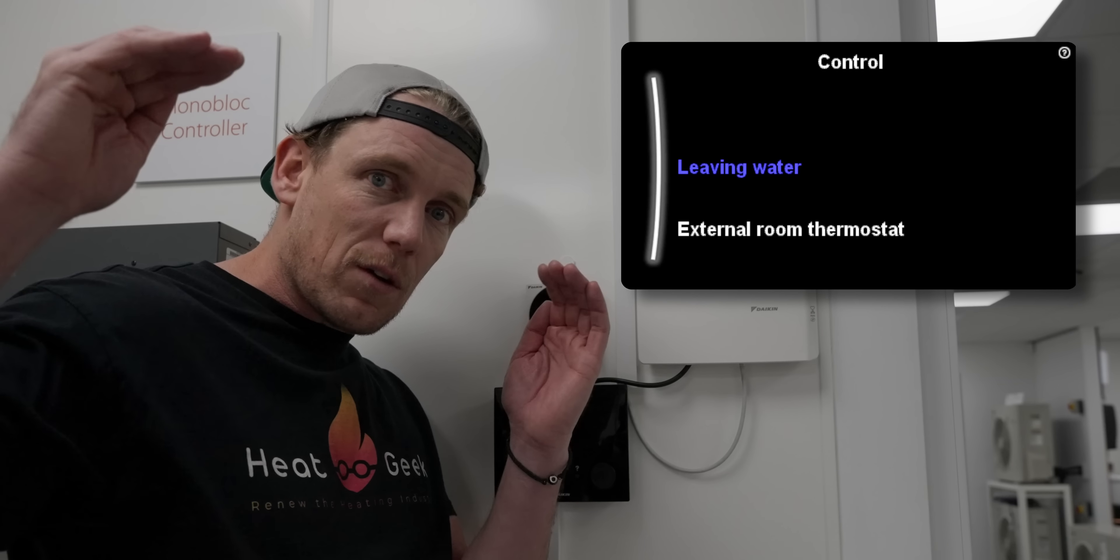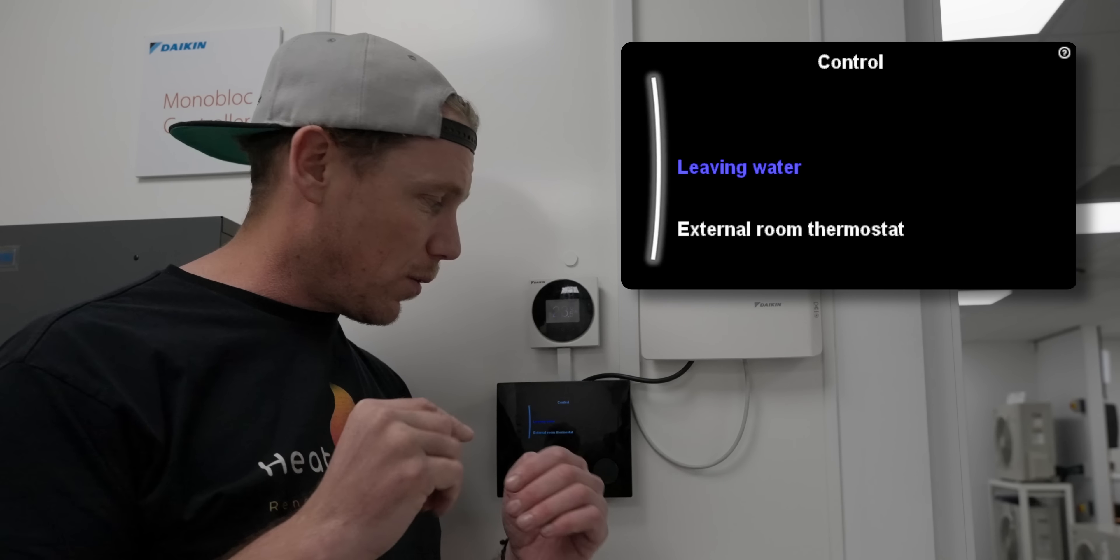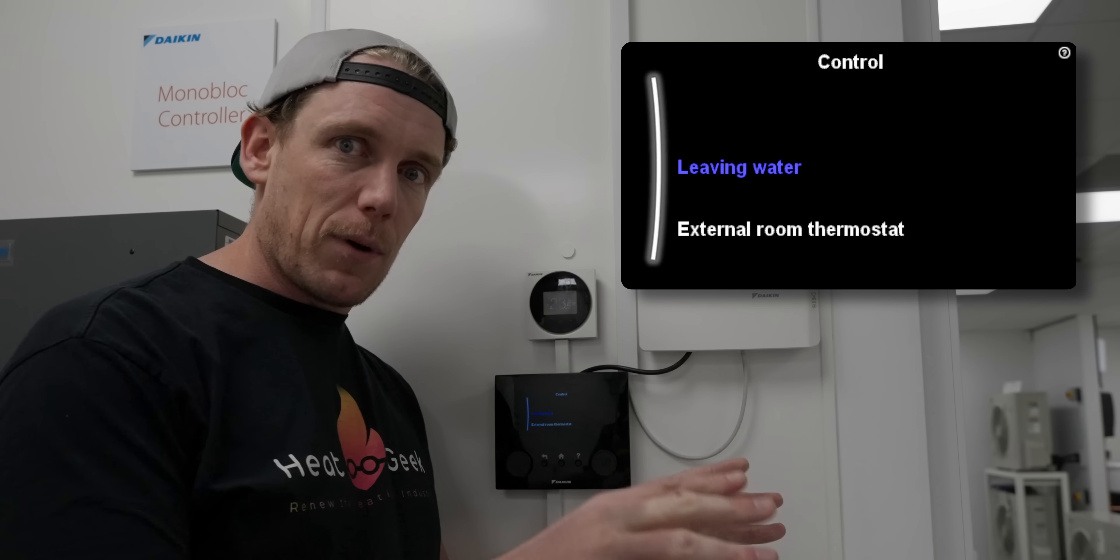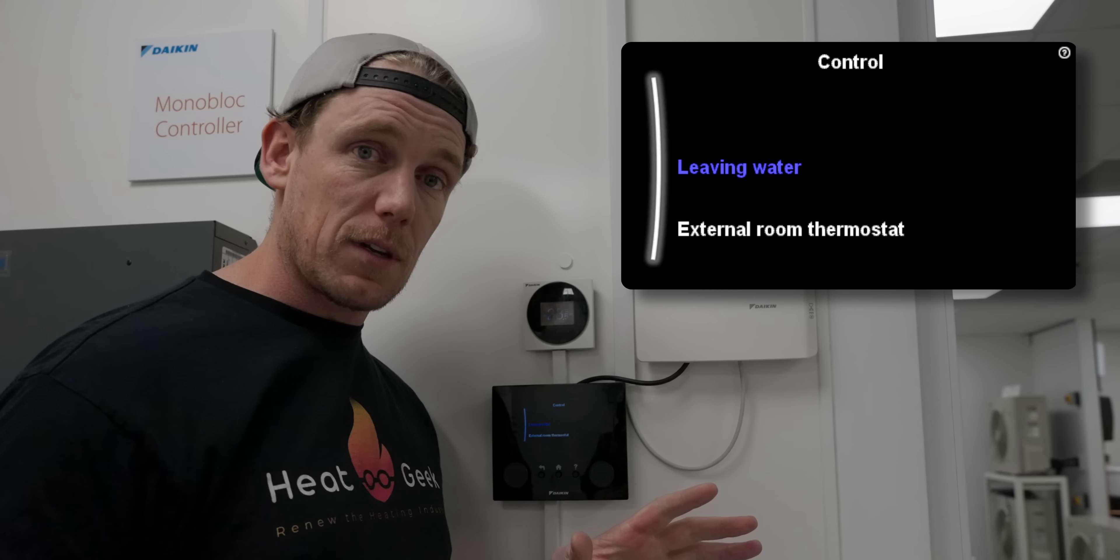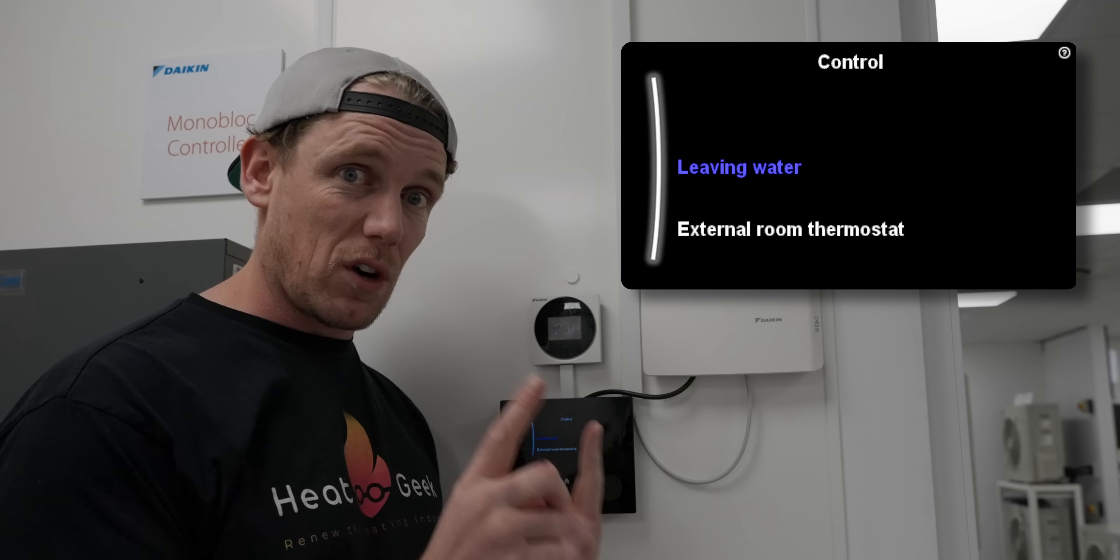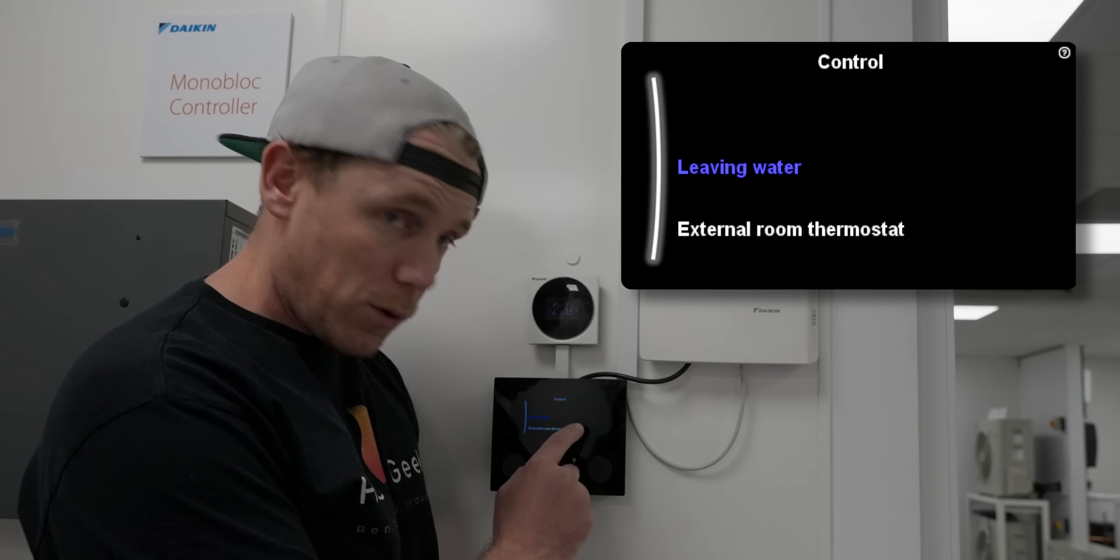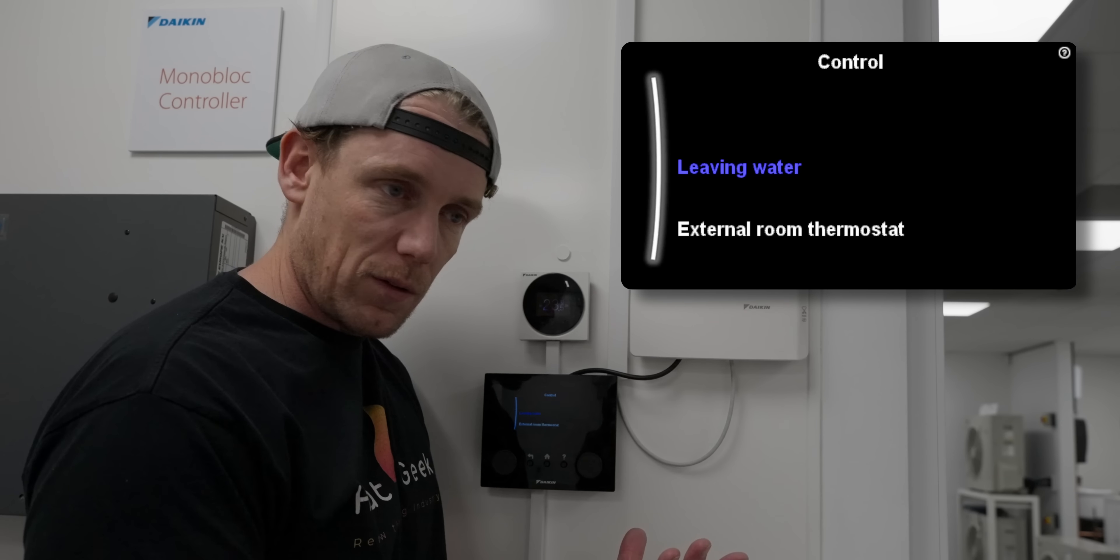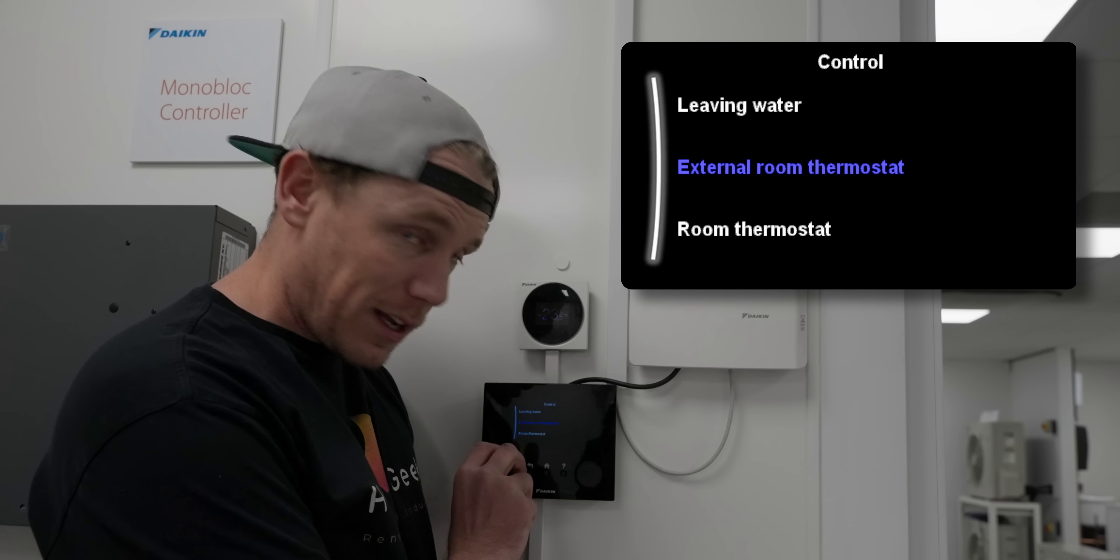Get it as comfortable as possible, then you can bring in your external controls so they close down the actuators as little as often and let the heat pump pump around as much of the system continually as possible. That's going to drive up your efficiency. So leaving water is pure weather compensation, like we refer to in our video, but all manufacturers have their own terms. External room thermostat is on-off, and room thermostat is a modulating room thermostat like we've got here.